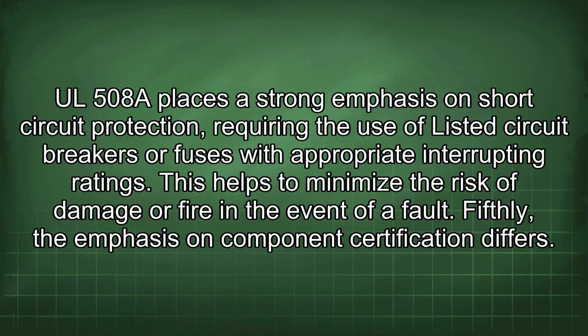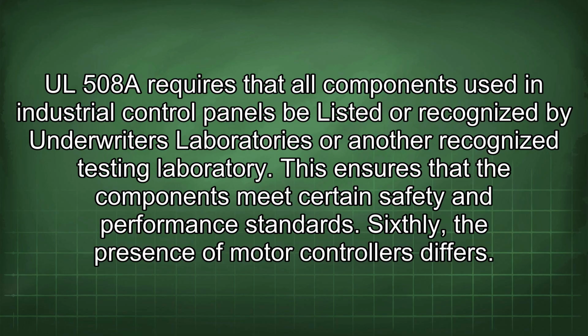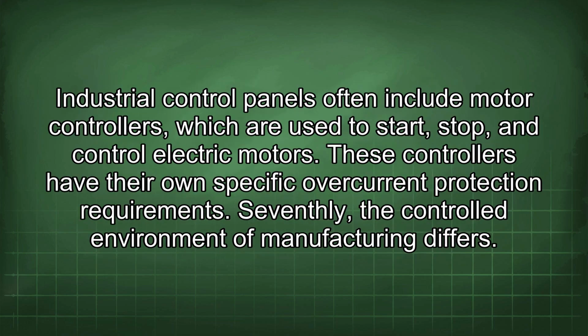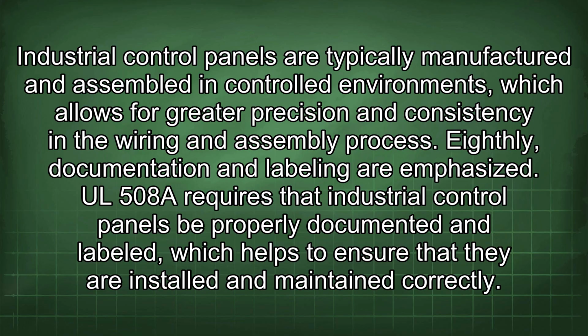Fifthly, the emphasis on component certification differs. UL 508A requires that all components used in industrial control panels be listed or recognized by Underwriters Laboratories or another recognized testing laboratory. This ensures that the components meet certain safety and performance standards. Sixthly, the presence of motor controllers differs. Industrial control panels often include motor controllers, which are used to start, stop, and control electric motors. These controllers have their own specific overcurrent protection requirements. Seventhly, the controlled environment of manufacturing differs. Industrial control panels are typically manufactured and assembled in controlled environments, which allows for greater precision and consistency in the wiring and assembly process. Eighthly, documentation and labeling are emphasized.